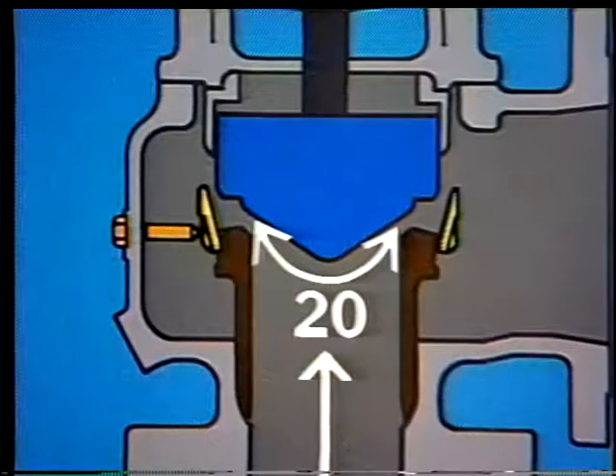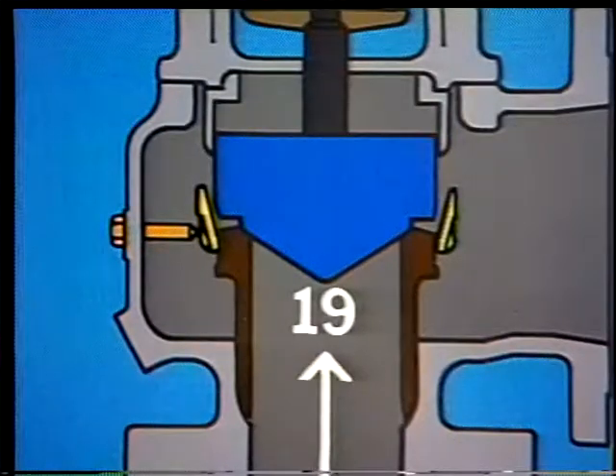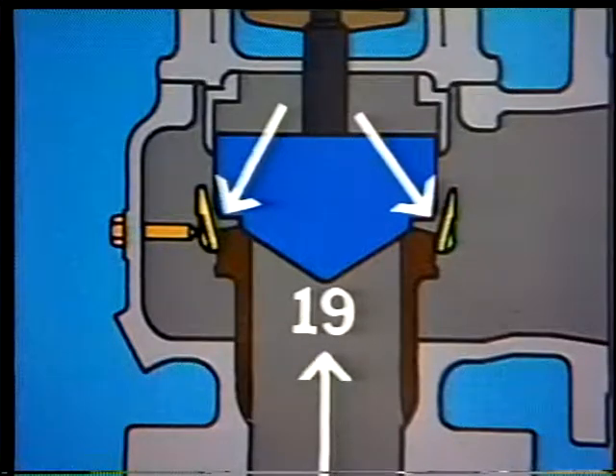Only when system pressure drops below the set point of the valve does the valve snap shut. The valve snaps shut instead of closing gradually to abruptly cut off the flow of steam, thereby minimizing steam cutting. A small cushion of steam trapped in the huddling chamber prevents the disc and seat from slamming together hard enough to be damaged.